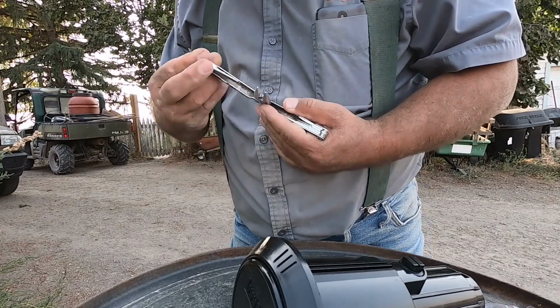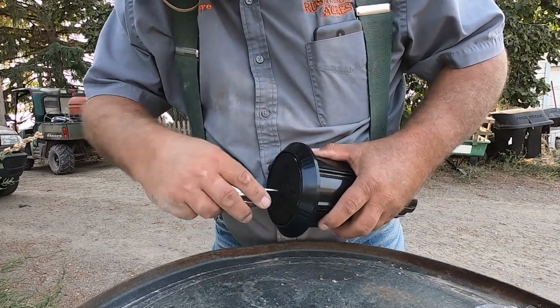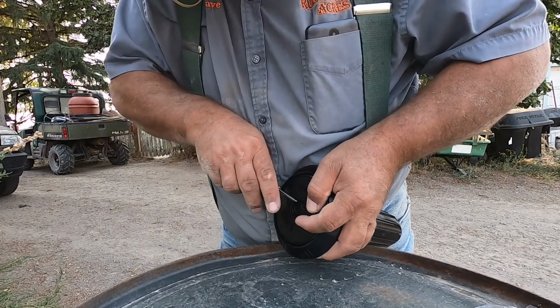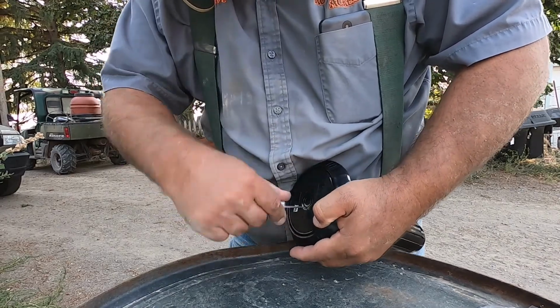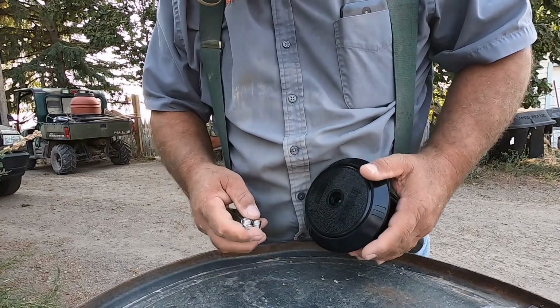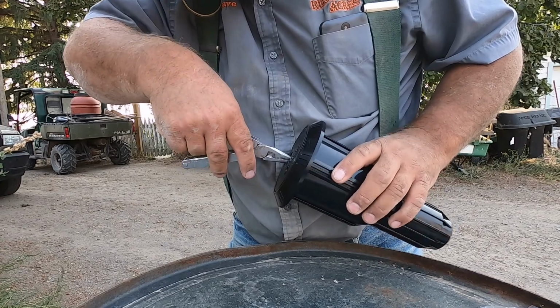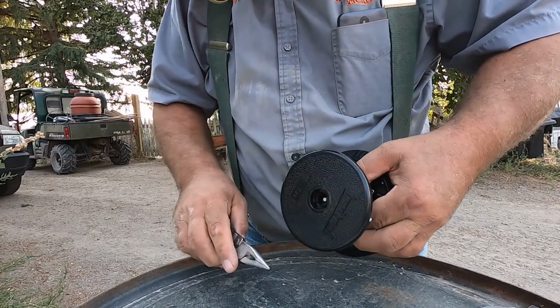Okay, there's something I didn't show anybody about doing this, and I guess I'd better. What we're running into is a situation where we're concerned about the amount of water getting down to the last sprinkler. If I can get this thing popped out of here. There it goes. What's going on is we have to change the nozzles in these sprinklers. And I don't have the tool with me to do it, so I've got to pull it up by hand, so you have to bear with me.